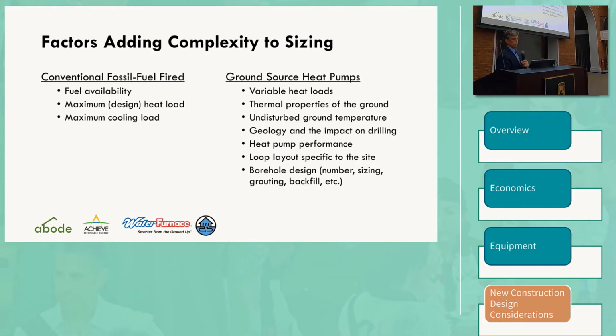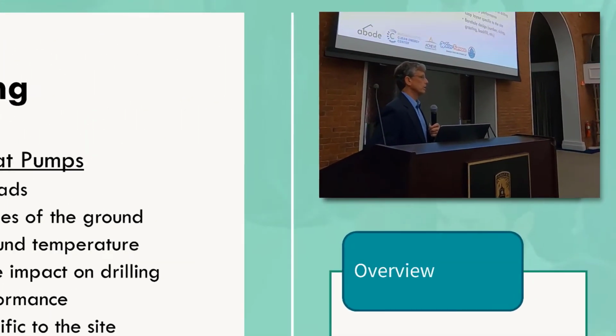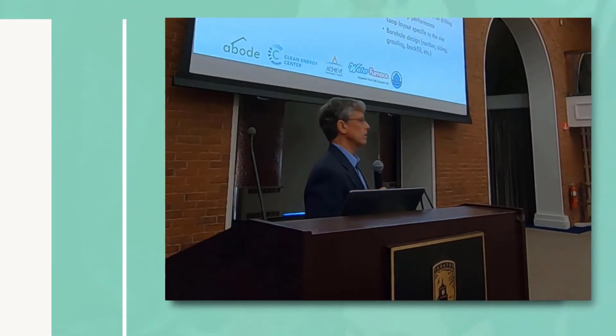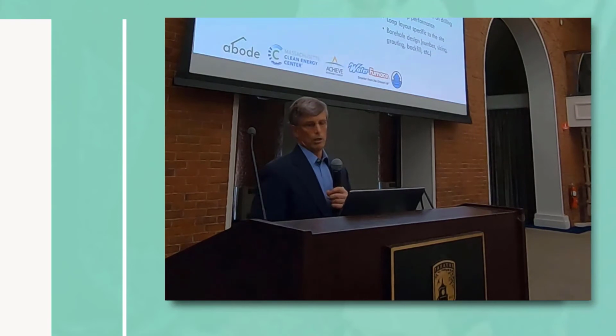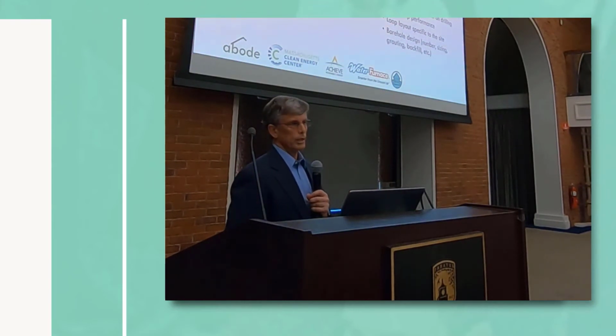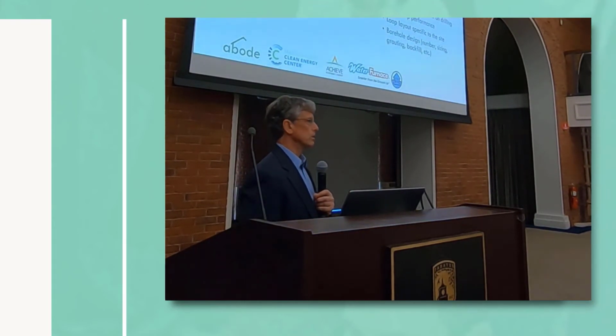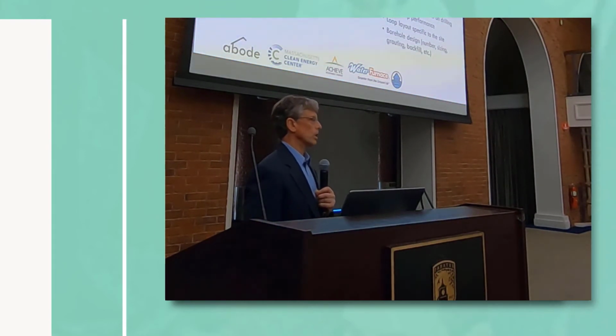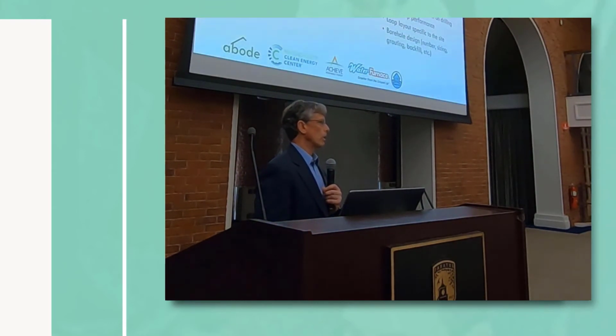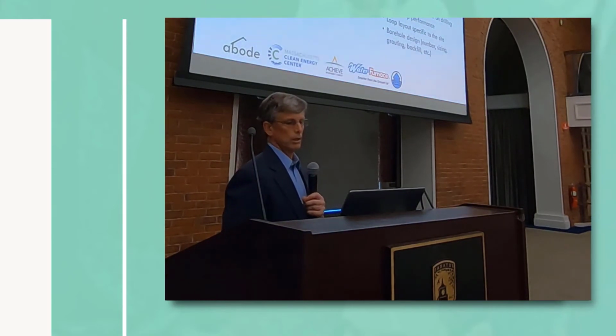With ground source, those systems have to pay attention to what the heating load for the house is and the cooling load as well. Our systems are normally designed much closer to the actual heating load and cooling load than the conventional systems are, which are often largely oversized. But in addition, you have to think about what the geology is and need to be working with a designer that understands that so that the ground source can be appropriately designed.